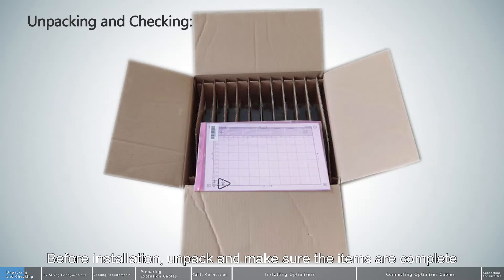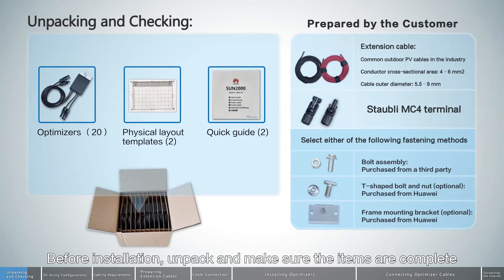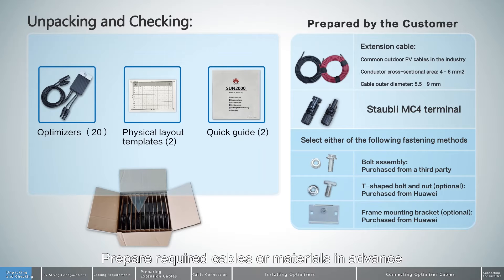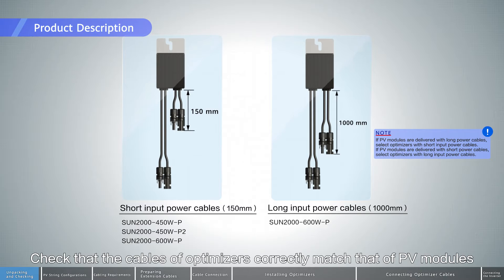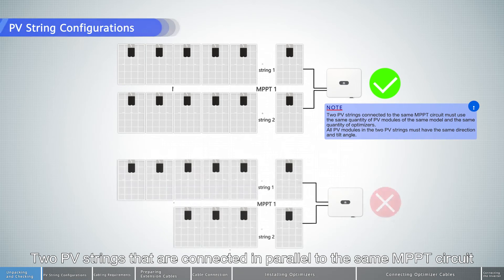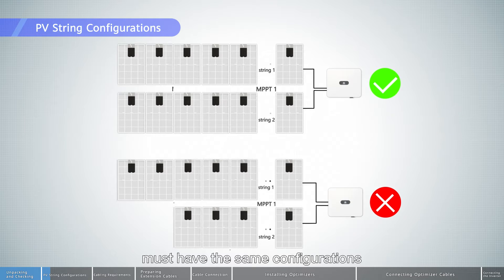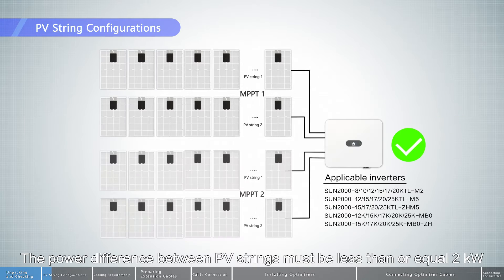Before installation, unpack and make sure the items are complete. Prepare required cables or materials in advance. Check that the cables of optimizers correctly match that of PV modules. Two PV strings that are connected in parallel to the same MPPT circuit must have the same configurations.